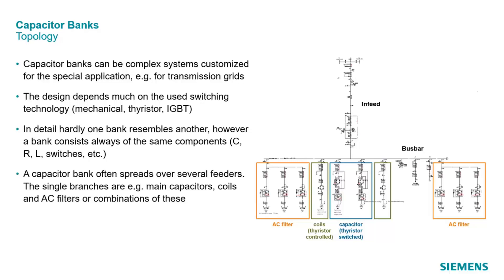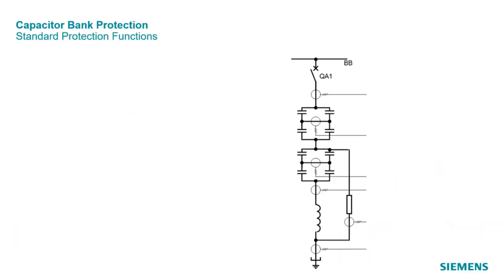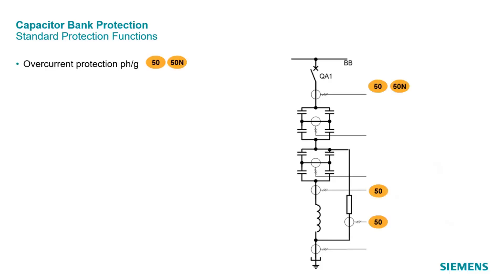A capacitor bank often spreads over several feeders. The single branches are, for example, main capacitors, coils, and AC filters or combinations of these. Some protection tasks can be solved with standard protection functions. The overcurrent protection for phase and ground faults is used to detect any kind of internal short circuit fault current, used as an overall protection for the complete capacitor bank, and can also be used inside the AC filter element.